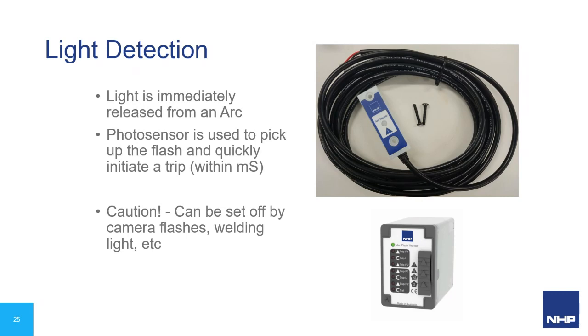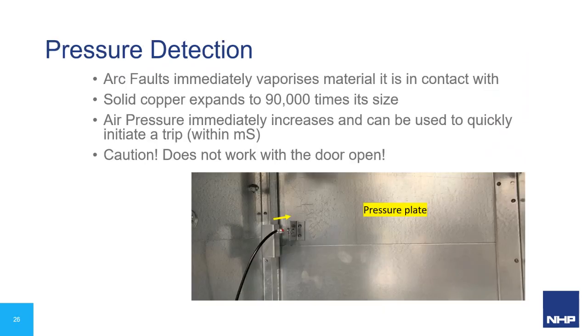On the right-hand side, there is the NHP variant. That's the arc sensor, and then the head unit down the bottom there initiates the trip with the upstream protection. Another option for detection is that you also get a large pressure wave when arc faults occur. Solid copper expands to 90,000 times its size when it goes from solid to gas. So the air pressure within an enclosure immediately increases and it can be used to initiate a trip. This is an example from our high voltage range. That pressure plate across the top gets pushed back, it's hinged, and that pulls on the cable going down the bottom left there. But again, caution: it won't necessarily work with the door open because that pressure wave may not be enough to push it as intended.